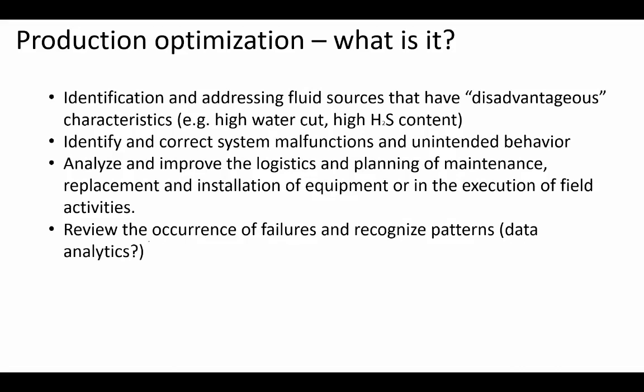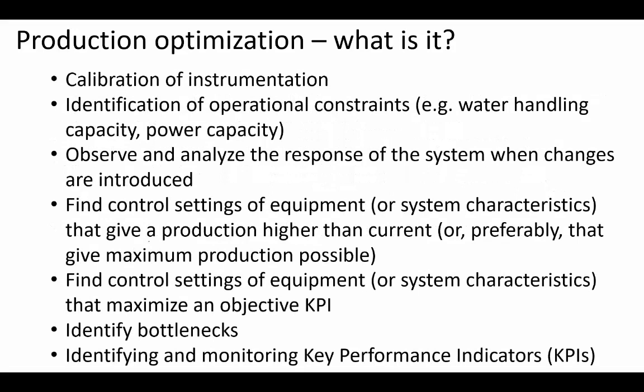You should review the occurrence of failures and recognize patterns — what might be called data analytics. For example, I was involved in a project where one pump was failing more often than another. It turned out one pump was always operating at a higher speed, which correlated with its higher failure rate. Recognizing this trend allowed a simple fix: keeping both pumps at the same speed.